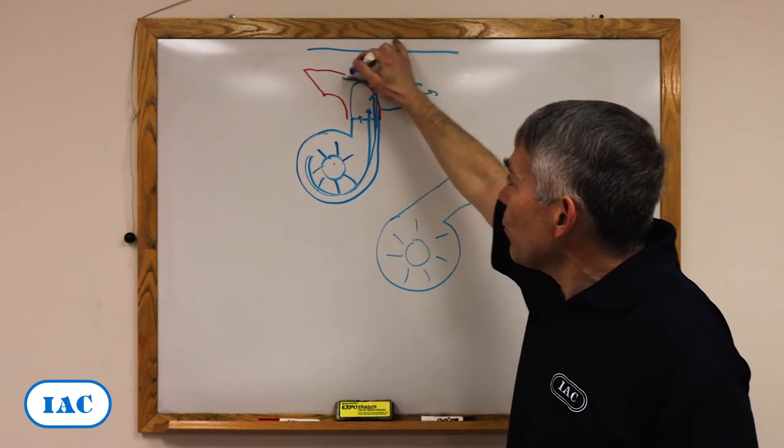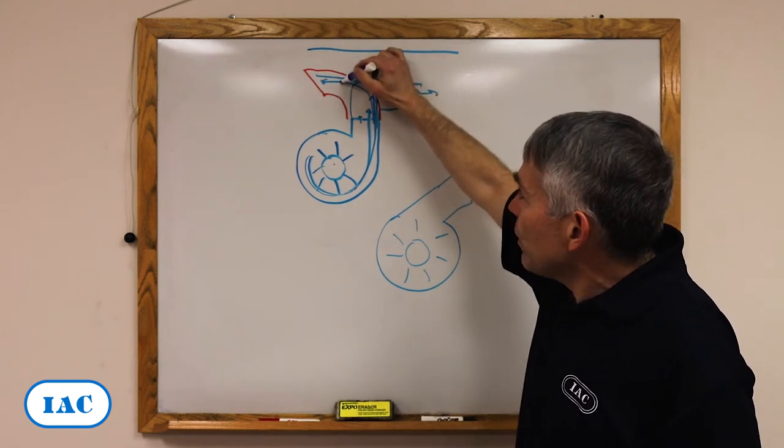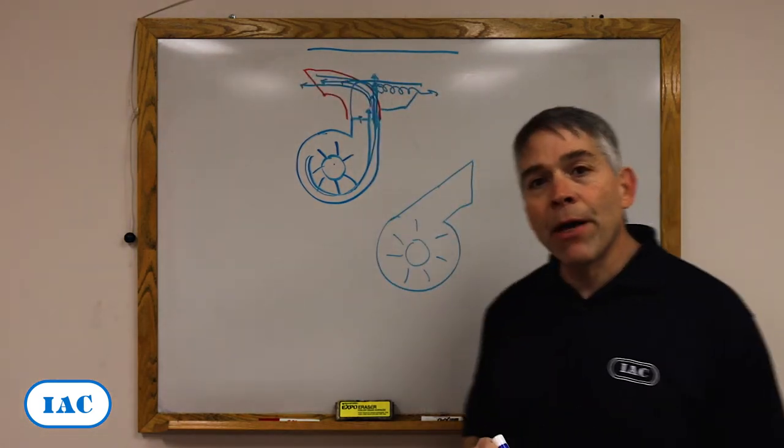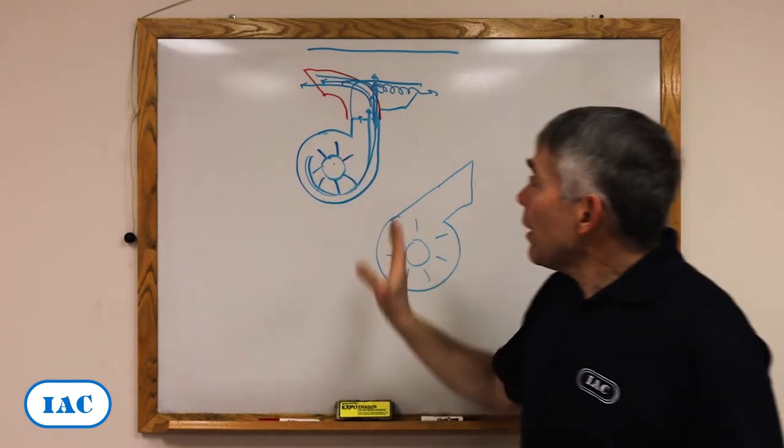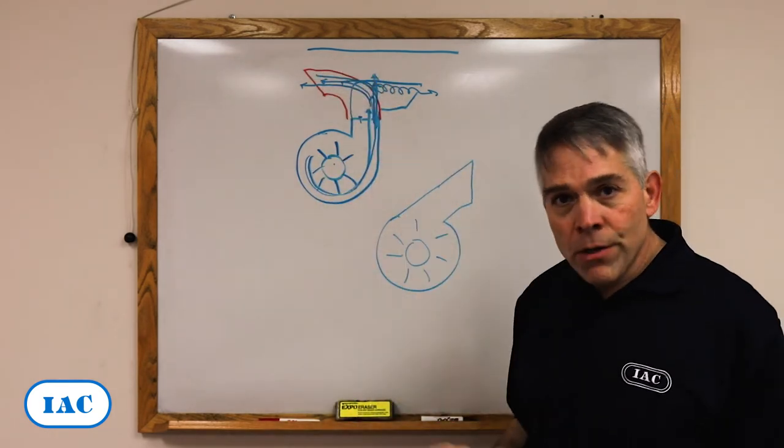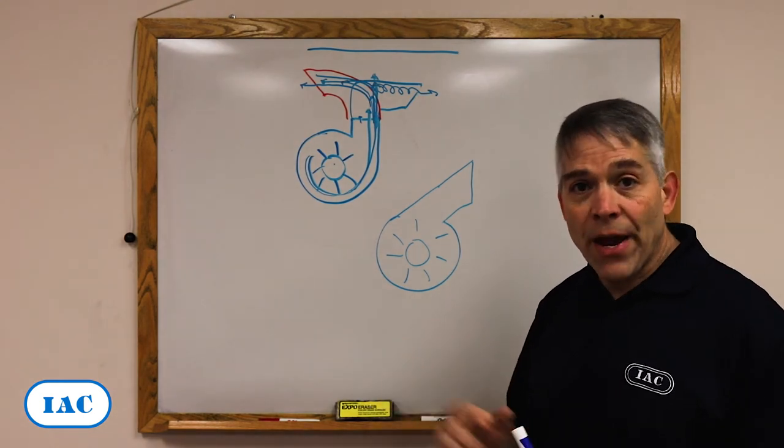If you turn it the other way, you get the higher velocity turning smoothly, and the fan works a lot better. So follow the way that the fan is letting that high velocity flow, and you get a lot more capacity, a lot more efficiency out of the same fan.